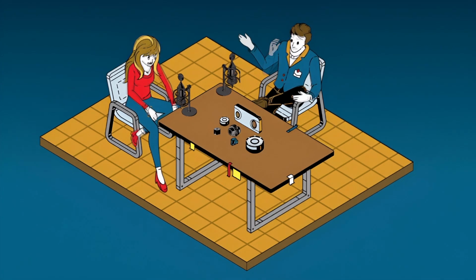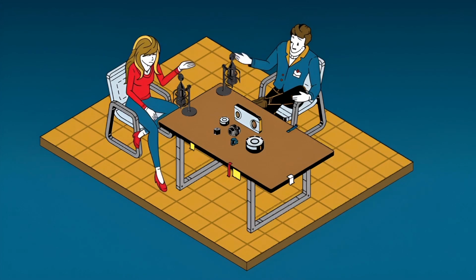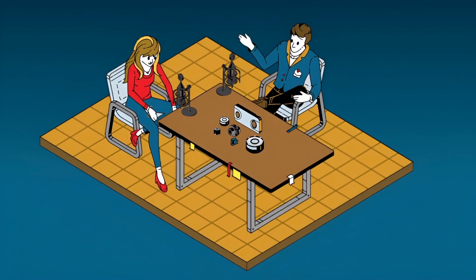So let's start with the things that actively sabotage your sensor. The danger zones, if you will. Good way to put it. If we understand the risks, we can mitigate them. We're calling this section 1, the 5 killers. These are the most common ways a load cell fails, or even worse, starts giving you bad data. And prevention is exponentially cheaper than dealing with data corruption or replacing equipment.